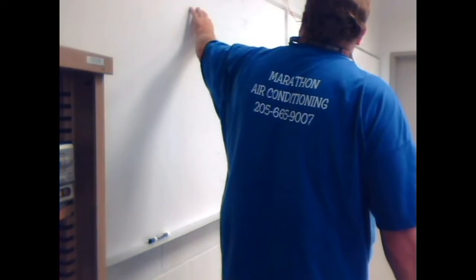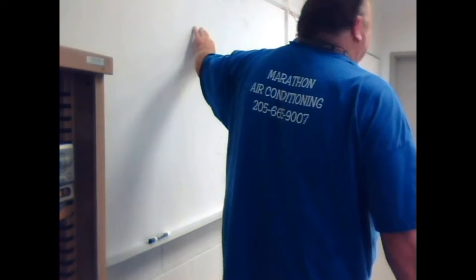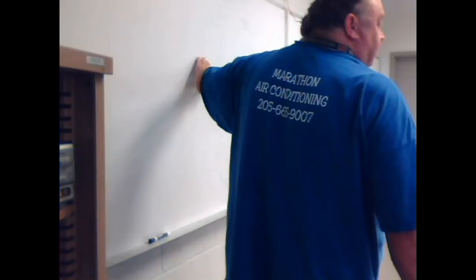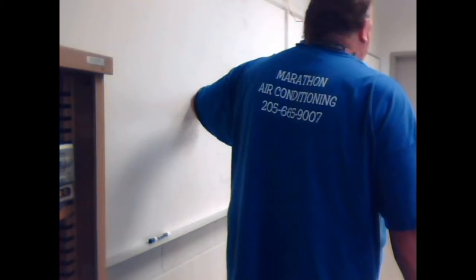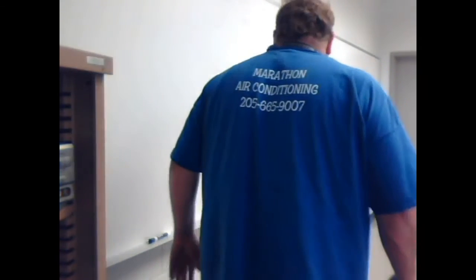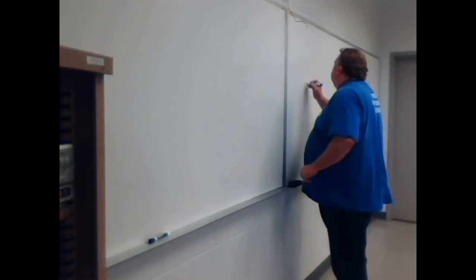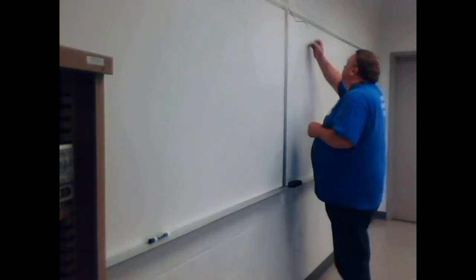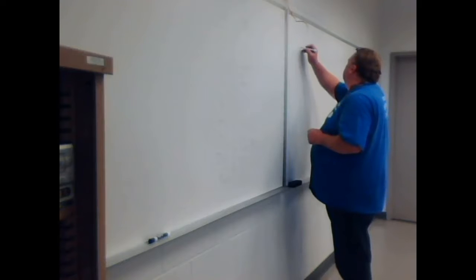Ambient 95, head pressure 240, suction pressure 50. My suction line temperature was 50, liquid line was 95. I'm using R22. I have a fixed metering device. It's a 3-ton AC, 10 SEER, and compressor amps are 16. So, with that stuff you would have gathered in the field, I expect you to construct it with a chart like we did the other day.